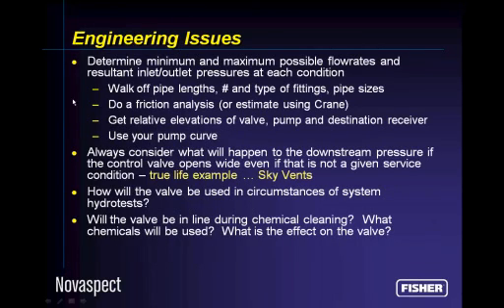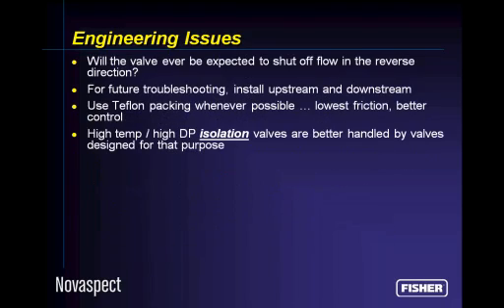Do the engineering that's required to know what the valve P1 and P2 are, okay? I won't bother to get into this story about sky vents because we're running short on time, but make sure that you know whether or not this valve will be used somehow for a hydro test. Know also, are you going to chemical clean the piping system with the valve in line? What chemicals are going to be used? How do you think they're going to affect the control valve? Okay. Will the valve ever be expected to shut off in the reverse flow direction?